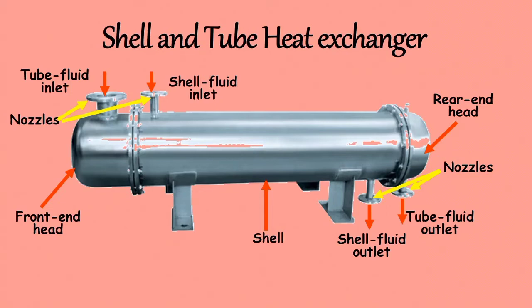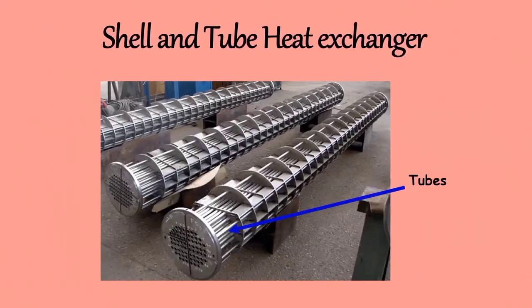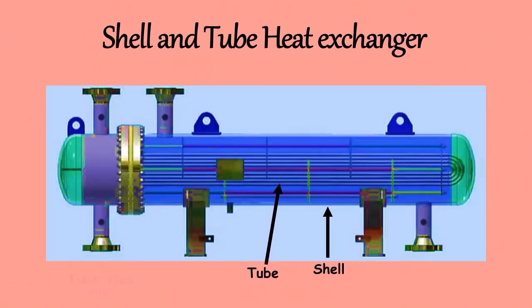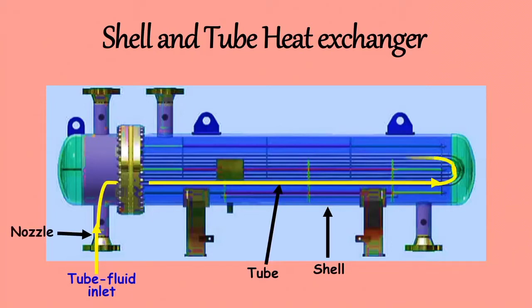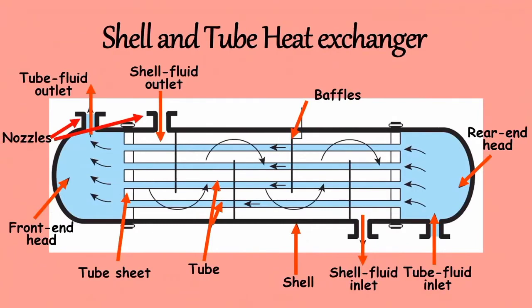The next component is the Tube. It is the most important part of the shell and tube heat exchanger. The tubes are placed in a tube bundle inside the shell, and are either rolled or welded to the tube sheet. The tube side fluid first enters a header through a nozzle, then flows through the tubes in parallel flow. Depending on how many passes through the tube, there are one pass or more than one pass types. In general, an even number of tube side passes are used.